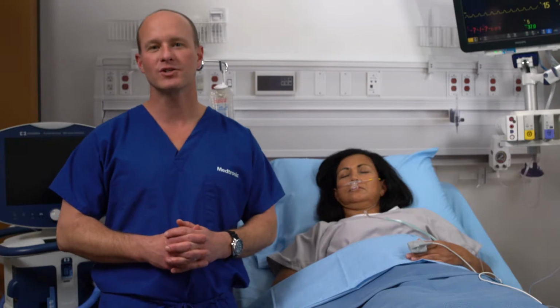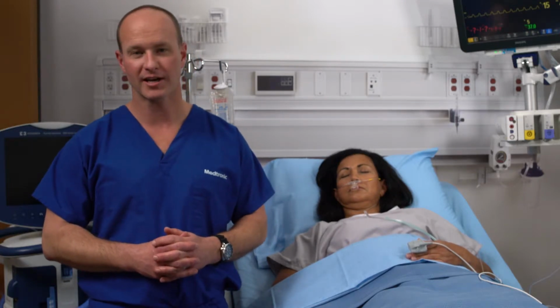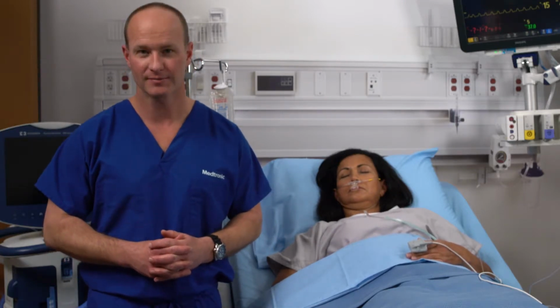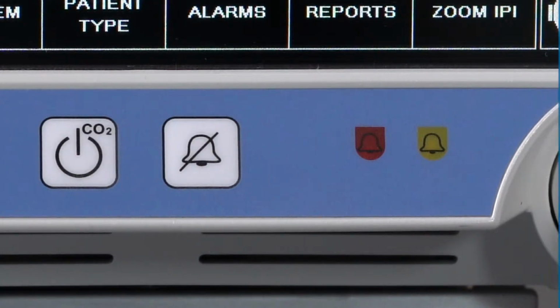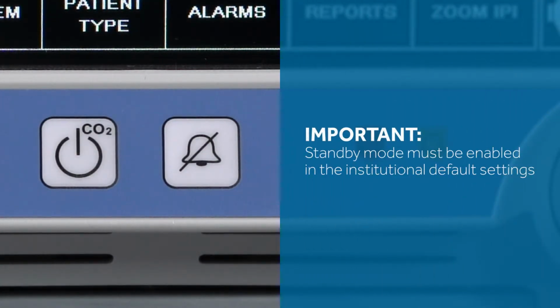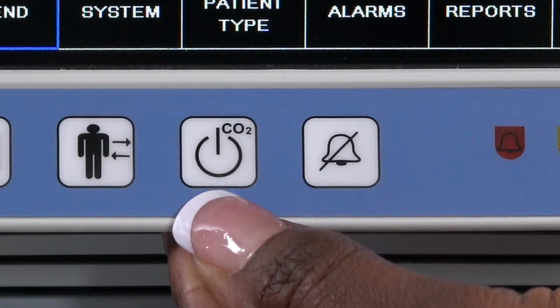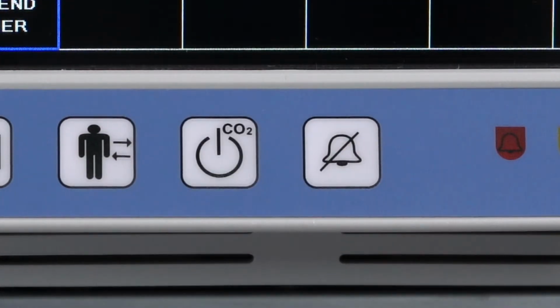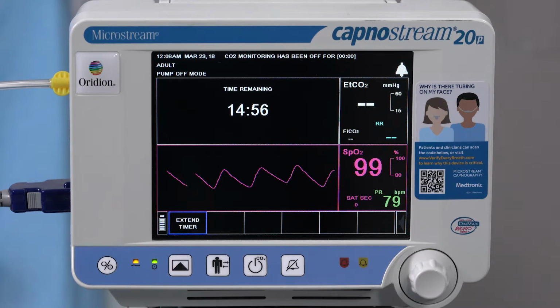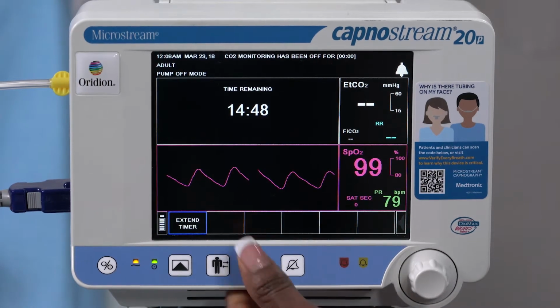Now the last two buttons on the right are very important to understand. They will become your best friends. They help minimize nuisance alarms. It's important to note that the standby mode will need to be enabled in the institutional default settings. Pump off button. A single press on this button pauses the CO2 pump for a preset amount of time. This allows you to disable the end-tidal CO2 so the sample line can be removed without creating an alarm. A single press turns it back on.